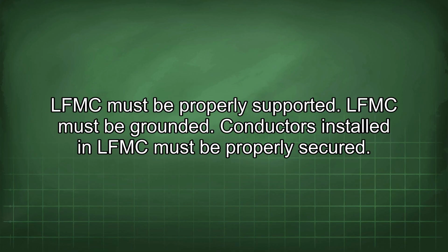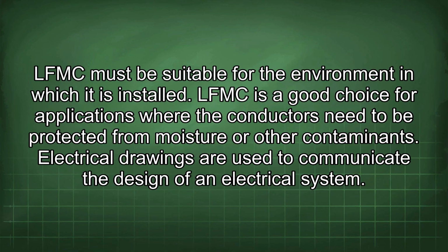The LFMC must be properly supported. LFMC must be grounded. Conductors installed in LFMC must be properly secured. LFMC must be suitable for the environment in which it is installed. LFMC is a good choice for applications where the conductors need to be protected from moisture or other contaminants.